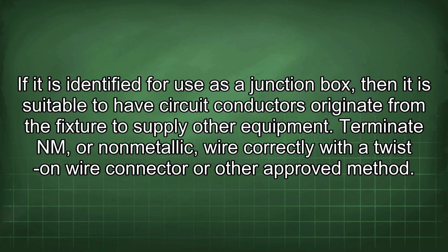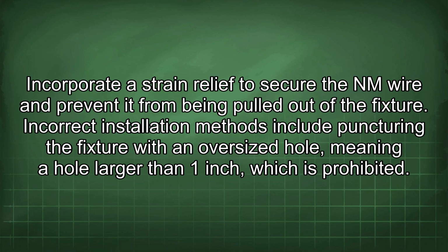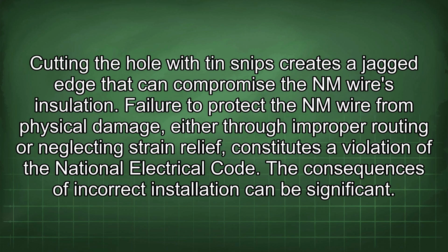Terminate NM or non-metallic wire correctly with a twist-on wire connector or other approved method. Incorporate a strain relief to secure the NM wire and prevent it from being pulled out of the fixture. Incorrect installation methods include puncturing the fixture with an oversized hole, meaning a hole larger than 1 inch, which is prohibited. Cutting the hole with tin snips creates a jagged edge that can compromise the NM wire's insulation.